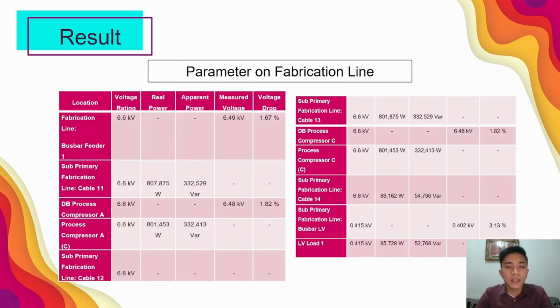So this is a table for the fabrication line. The fabrication line is the heaviest load being placed. The primary load such as a process compressor is rated at 6.6 kV. So the voltage supply for the busbar feeder 1 is coming from the SPDB 1, which is stepped down from 11 kV to 6.6 kV. The measured voltage at the busbar feeder 1 is 6.49 kV, which has a 1.67% difference from the rated voltage.